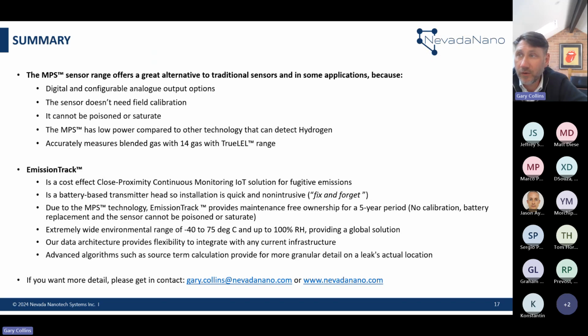The sensors don't need field calibration. Bump testing is a safety element and might be needed from a legislative perspective, but you don't need to calibrate the sensor for the life of it, and it cannot be poisoned or saturated. So where other sensors can fail with no feedback that they've poisoned, the MPS will provide that detail, whether it's an analog signal of a failure or a status flag, providing far more information on the sensor's current state and condition.